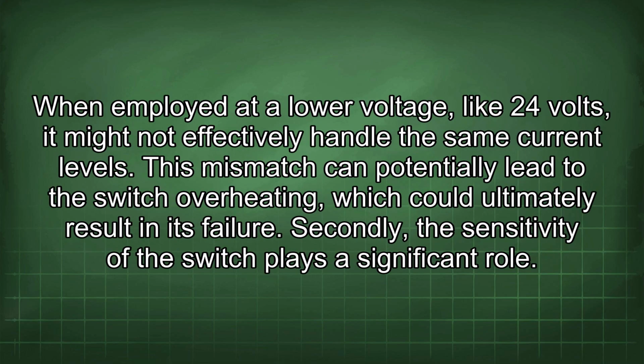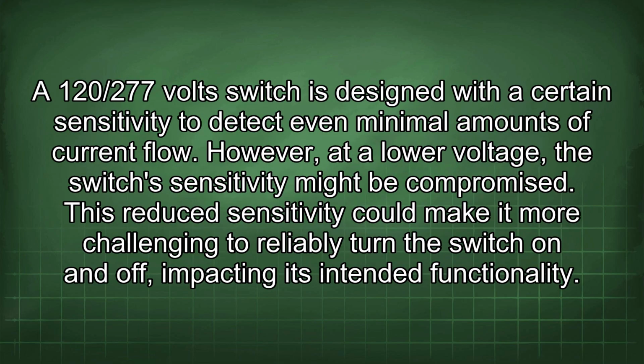When employed at a low voltage, like 24 volts, it might not effectively handle the same current levels. This mismatch can potentially lead to the switch overheating, which could ultimately result in its failure. Secondly, the sensitivity of the switch plays a significant role. A 120/277 volts switch is designed with a certain sensitivity to detect even minimal amounts of current flow.